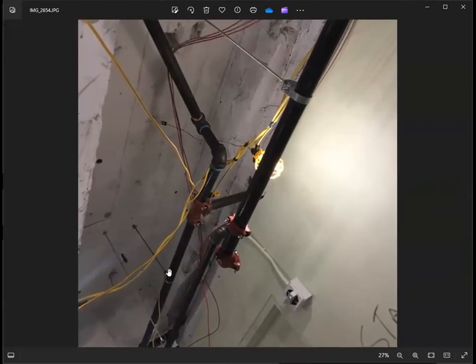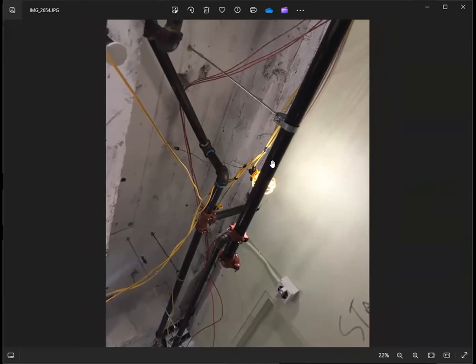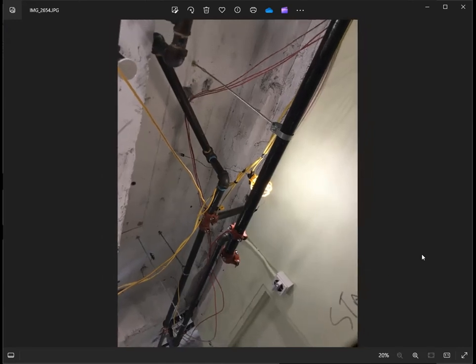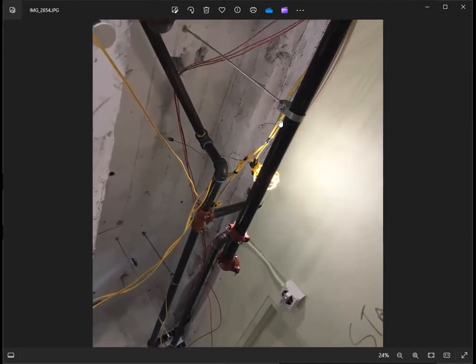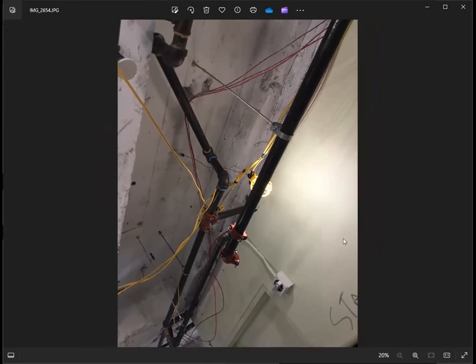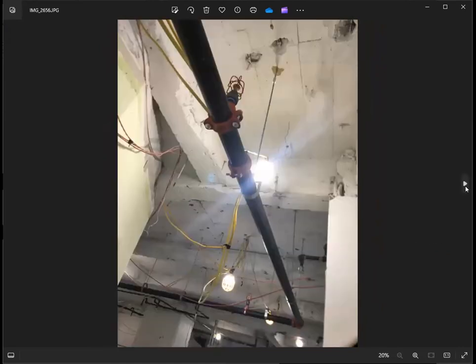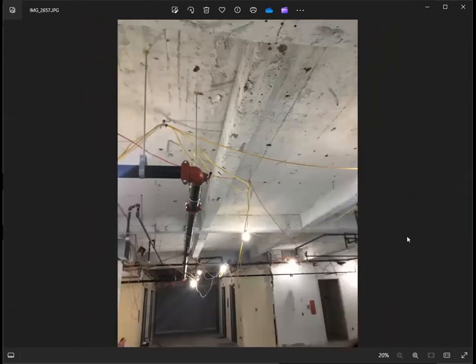The support, so pipe support should be, I could say there's a requirement, but to be safe, most likely they put the supports at every turn of the pipe and horizontally probably every 6 feet interval spacing, just to be supported. But the support is also required depending on the size of the pipe. So as long as it's supported, and yeah, every turn they have support, I believe it will hold and at least comply with the minimum hanger requirements.